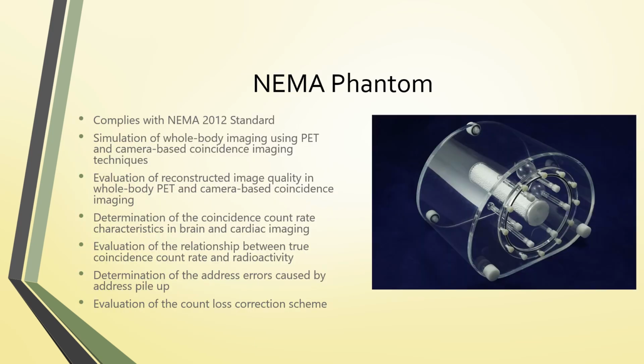This is a NEMA phantom. It allows for simulation of whole body imaging using PET and camera-based coincidence imaging techniques, and it's used for evaluation of reconstructed image quality in whole body PET and camera-based coincidence systems. It allows for the determination of coincidence count rate characteristics for brain and cardiac imaging, evaluation of the relationship between true coincidence count rate and radioactivity, determination of the address errors caused by address pileup, and evaluation of count loss correction schemes.